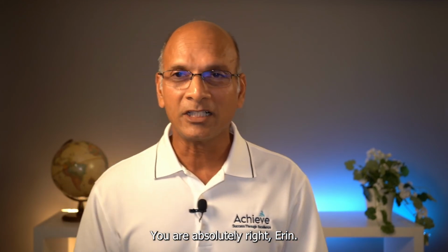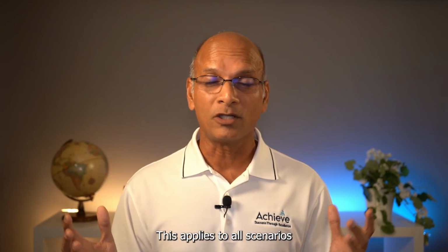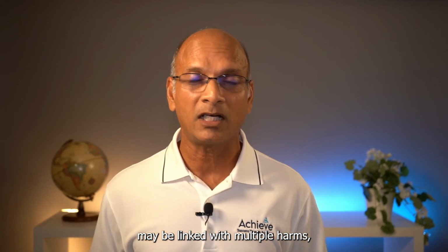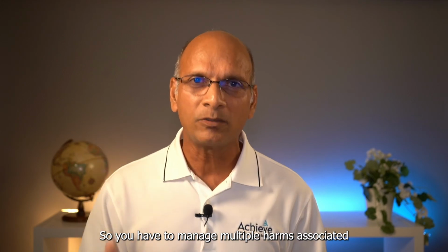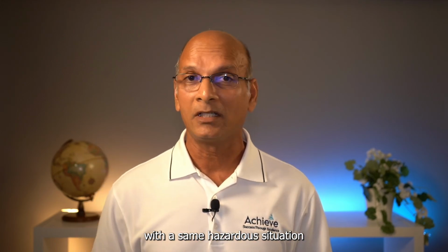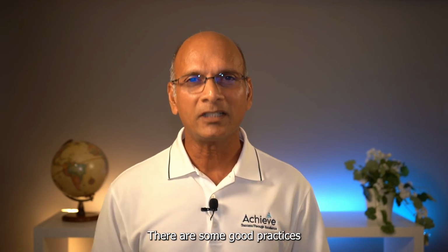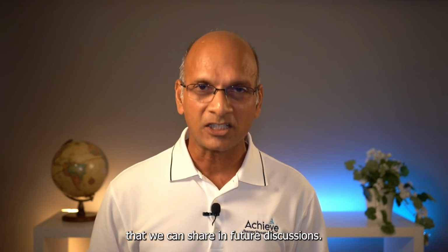You are absolutely right, Erin. This applies to all scenarios. Any hazardous situation may be linked with multiple harms, not just explants. So you have to manage multiple harms associated with the same hazardous situation in almost all scenarios. And how you do it, there are some good practices that we can share in future discussions.